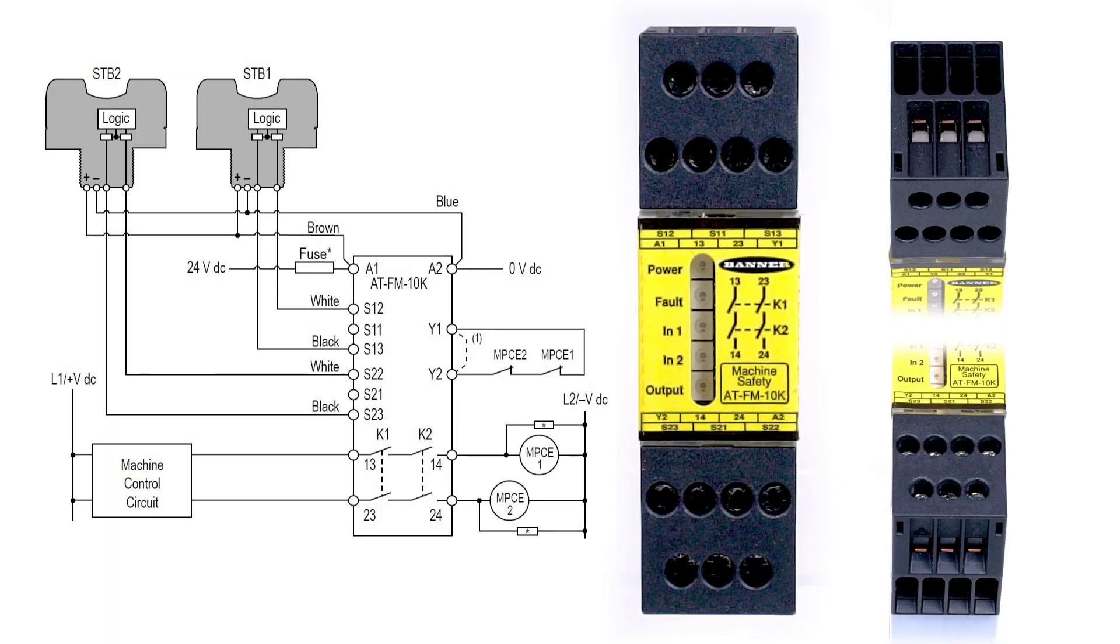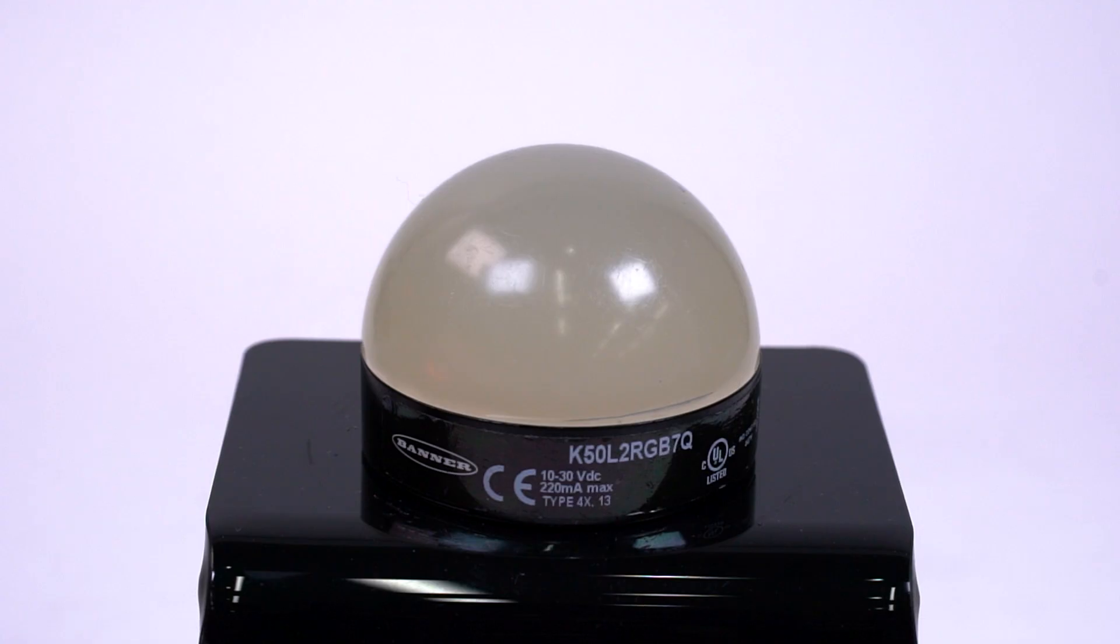The relay module's safety outputs are provided via Terminals 13 and 14 and 23 and 24. Connect the machine control circuits to the first terminal of each pair and connect your machine contactors to the second terminal of each pair. To simulate this, we are using a separate power supply and a K50 indicator.